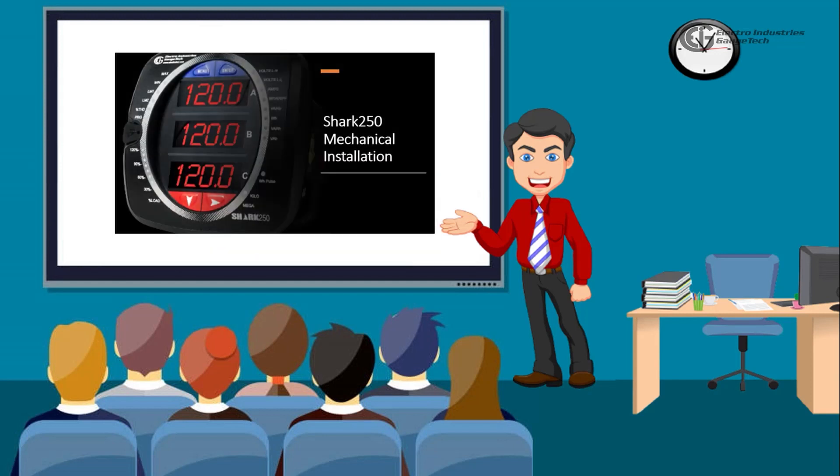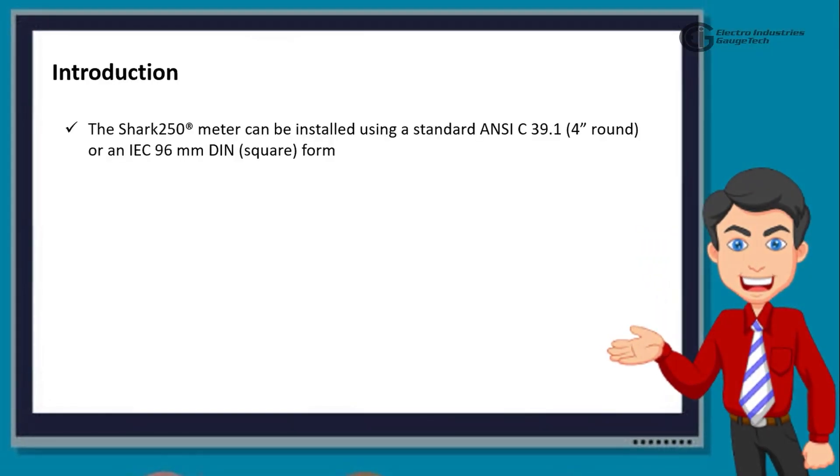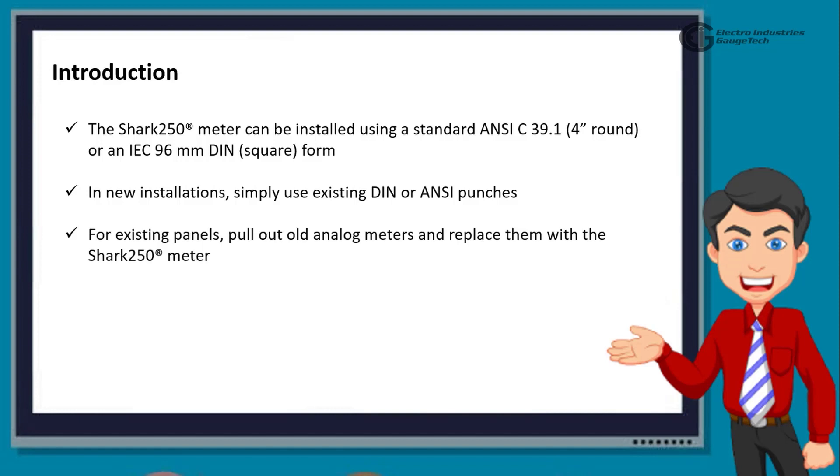We will begin with mechanical installation. The Shark 250 meter can be installed using a standard ANSI C 39.1, 4 inches round, or an IEC 96mm DIN square form. In new installations, simply use existing DIN or ANSI punches. For existing panels, pull out old analog meters and replace them with the Shark 250 meter.